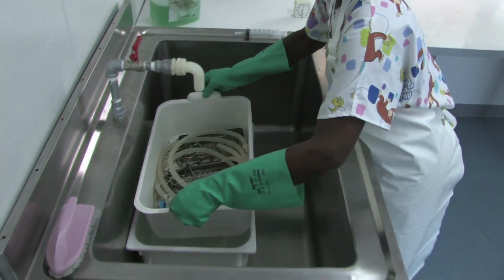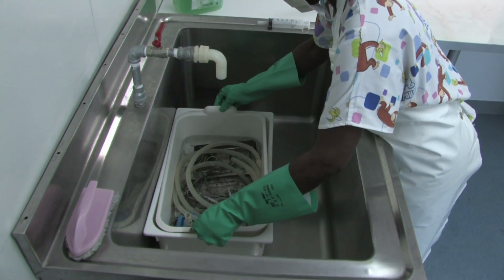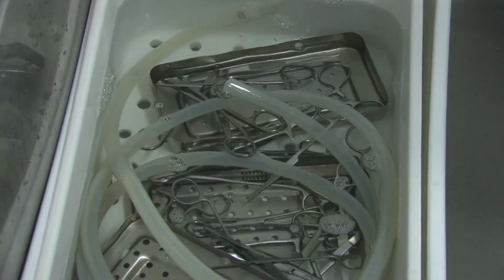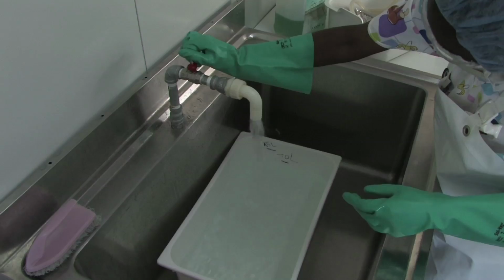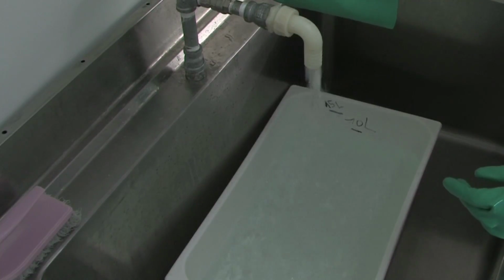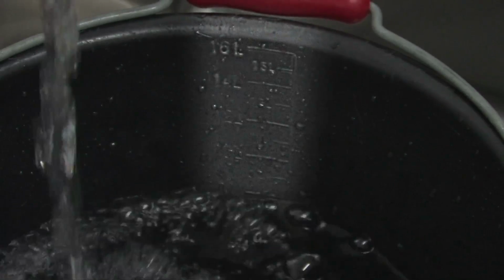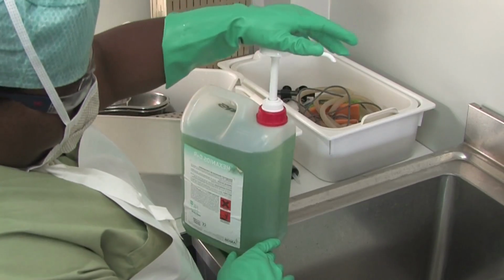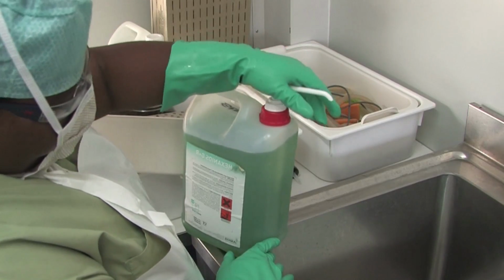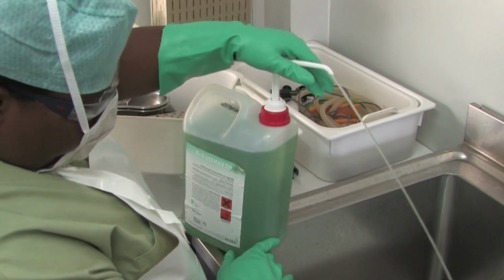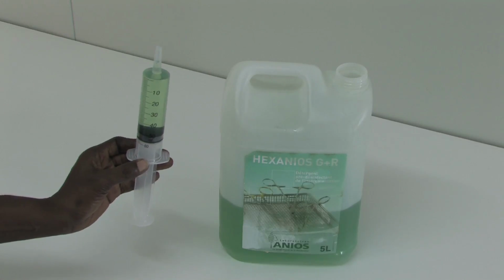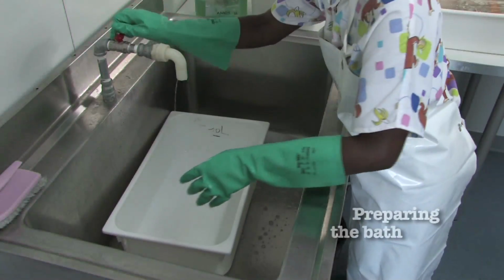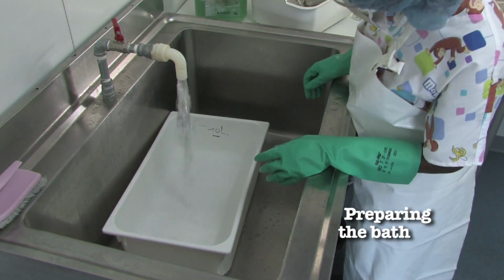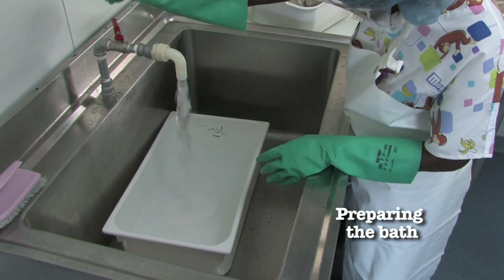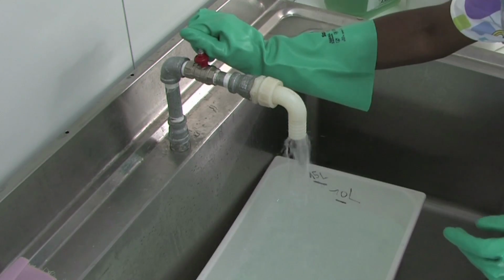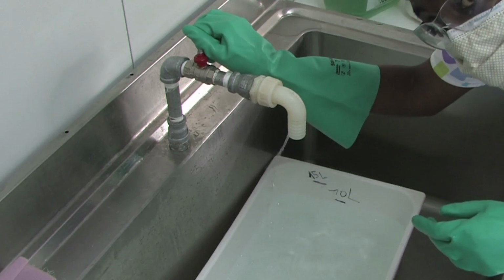Pre-disinfection consists of letting the materials soak for at least 15 minutes in a detergent disinfectant solution. This requires a graduated tub, a detergent disinfectant product in a bottle with a pump dispenser, or a 50 milliliter syringe. To prepare the bath, begin filling the graduated tub with water. Turn off the water before reaching the desired volume.